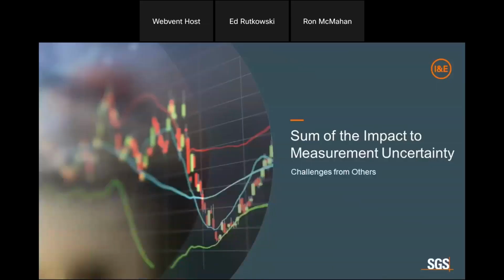And so the next thing that I think is so interesting is when you go through a calibration process like this and you're looking for the uncertainty, measurement uncertainty, that's the key. And you have to do everything you can to eliminate anything that can cause uncertainty in your method. And using the right test gas, the right things, the right instruments, the right calibrations, on and on and on in the process. So I want to show you something that is, to me, why CIHs need to be involved and what you need to be looking for or looking at when it comes to the data that's in these instruments.